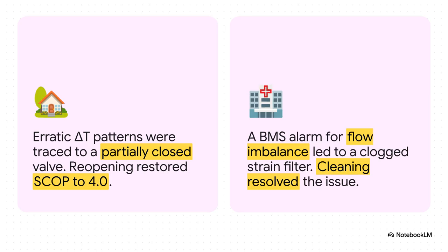These case studies illustrate the effectiveness of digital diagnosis. In a residential setting, data analysis of erratic temperature differentials identified a partially closed valve. In a hospital, a building management system alarm indicating a flow imbalance led technicians directly to a clogged filter. Both examples demonstrate how monitoring data can lead to efficient physical solutions.